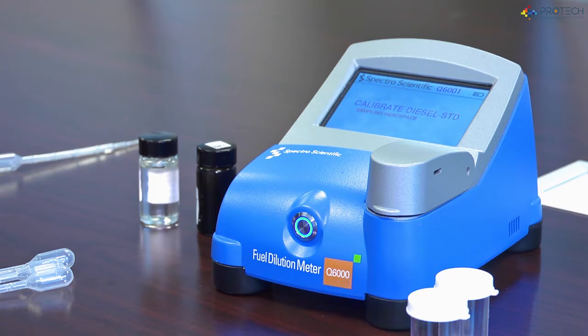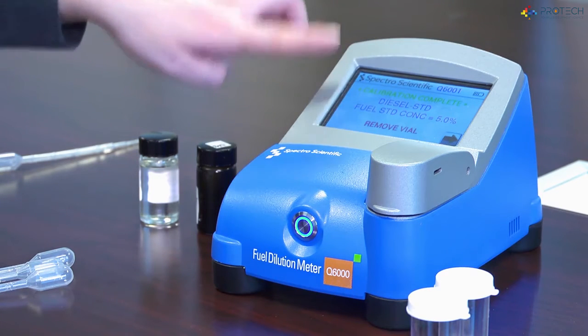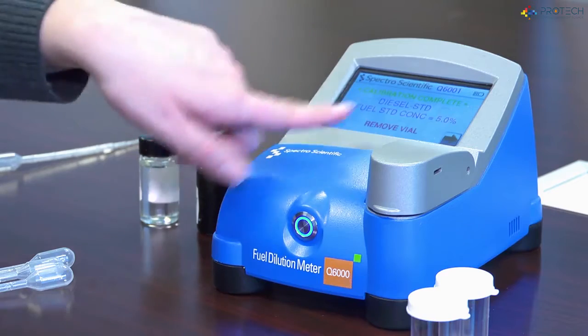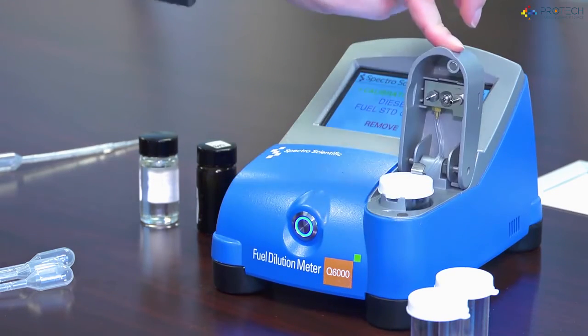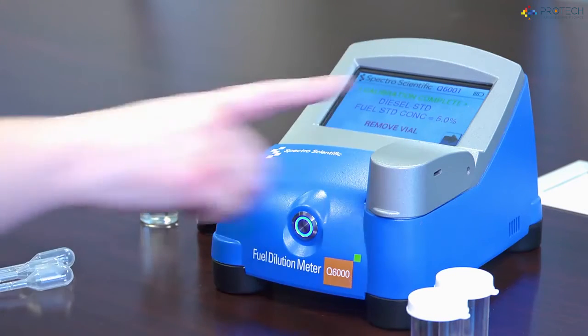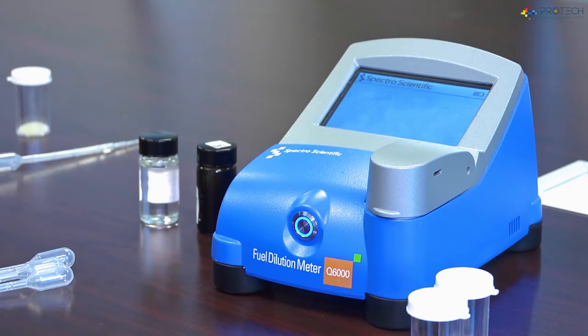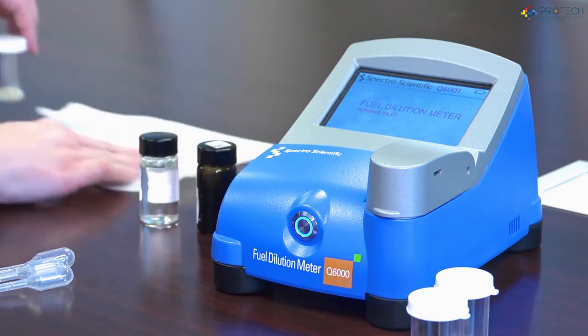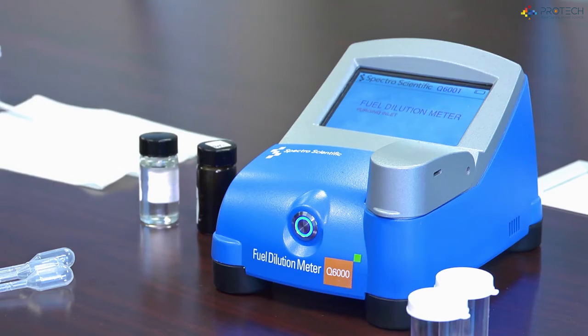Sampling headspace. Remove vial. So it says calibration successful. So I push the arrow key, and it reminds me which calibration slot I put it into, the concentration that I put in, and it asks me to remove the vial. So I'm going to remove the vial, close the lid, and then push next. Purging inlet. Now it's purging so that it's ready for the next sample.